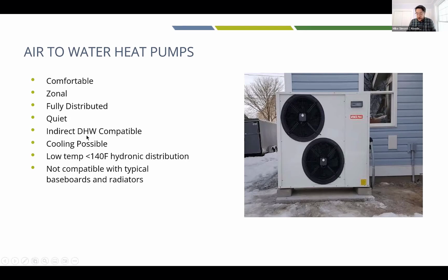Some other benefits with air-to-water is you can do domestic hot water—the hot water coming out of your sinks and showers. With the other heat pumps we've talked about, there's no solution with that split outdoor unit heating and cooling the home to also handle domestic hot water. So for that, you need a different type of heat pump system, or another technology like solar thermal. Air-to-water heat pumps can do cooling, but it's a lot harder than with air-to-air heat pumps.